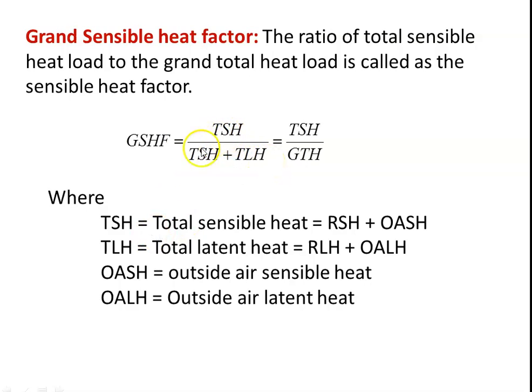And what is the total sensible heat? Total sensible heat equals room sensible heat, what we calculated earlier in the previous calculation, plus OASH, where OASH is the outside air sensible heat. And total latent heat is equal to room latent heat, what we calculated earlier, plus OALH.